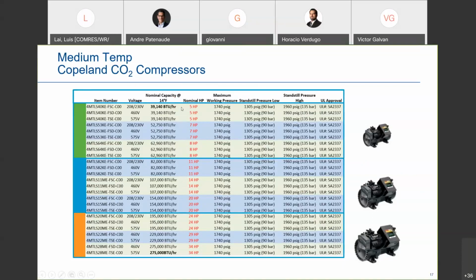The next models that were released here in North America were the 5 to 8 horsepower. So somewhere from 40,000 BTUs to 63,000 BTU. The third grouping is down here, 24 to 34. The 34 has not yet been launched in North America, but we do have the 24 and the 29 horsepower, so almost 200,000, 230,000 BTUs. The largest displacement here when it's released is 275,000 BTUs, that's at plus 14. When you're at plus 20, it's somewhere around 310,000 BTUs or 25 to 26 tons.